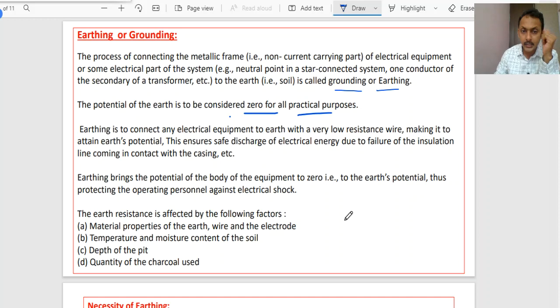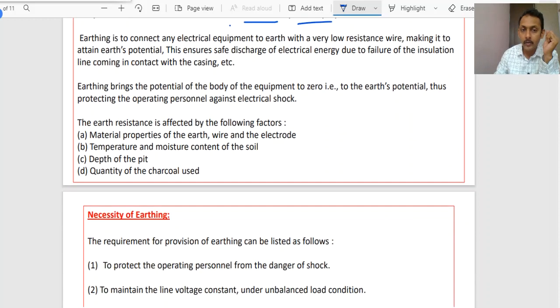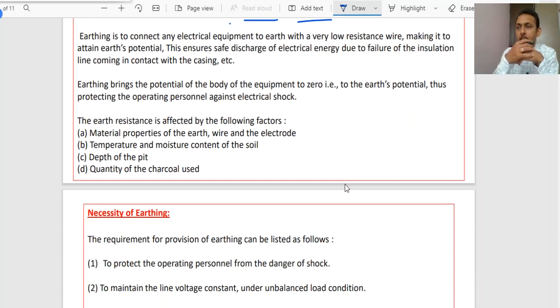Now the earth resistance will get affected by the following factors. It depends upon the material properties of the earth wire and the electrode, and also upon the temperature and moisture content of the soil. It depends upon the depth of the pit and the quantity of charcoal we have used. While making the earthing connection, these are all the arrangements we have to make, and we have to take care about all these properties, right?